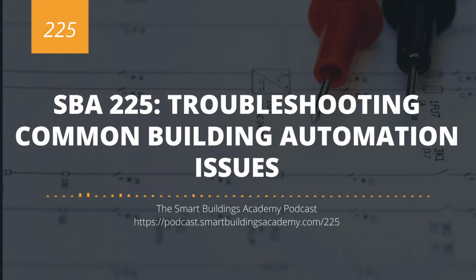And usually this comes in the form of, hey, we're hot call to hot call. We're basically being a firefighter and we're just reacting, and we're not being strategic in our reaction. And sure, you can do a short-term fix, turn the flow up to 100% and just douse the space in conditioned cold air. And that may solve the problem. That may lower the temp, but then you might have subcooling. You're actually starving boxes in other spaces and causing hot spots in there. And then it becomes a giant game of whack-a-mole. And so you've got to have some process.